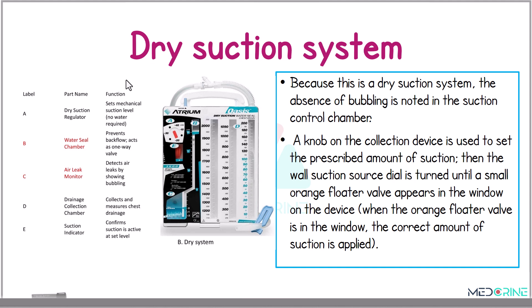Looking at the parts of a dry suction system: we have a dry suction regulator on one side; a water seal chamber labeled B, which prevents backflow and acts as a one-way valve; an air leak monitor, which detects any air leaks by showing bubbles; a drainage collection system where we collect and measure chest drainage, just like a wet suction system; and lastly a suction indicator to confirm that suction is active at the set level.